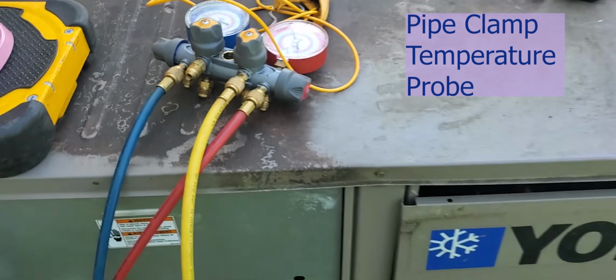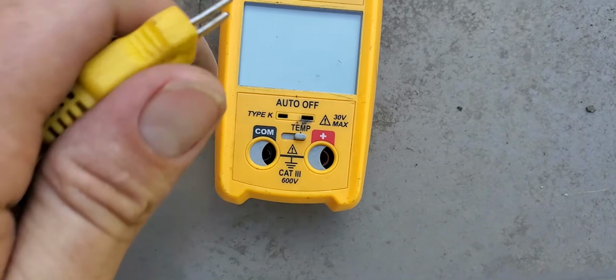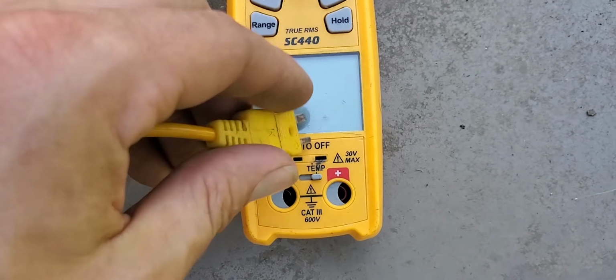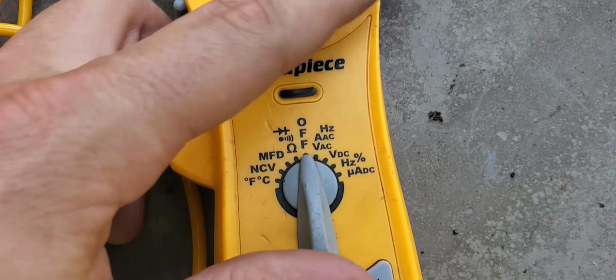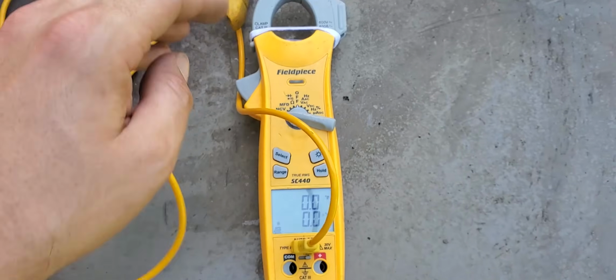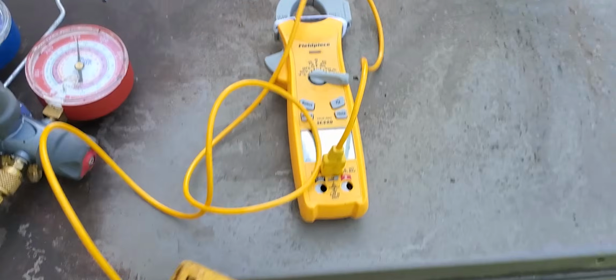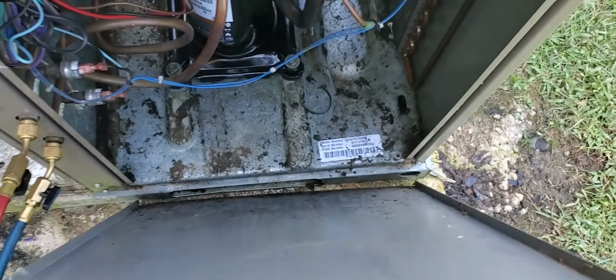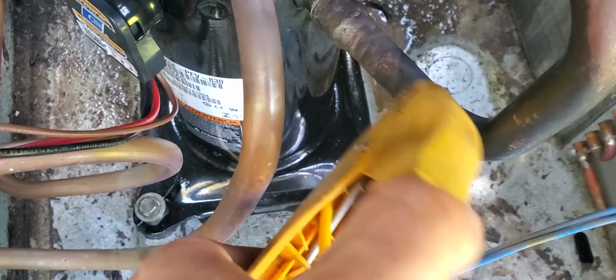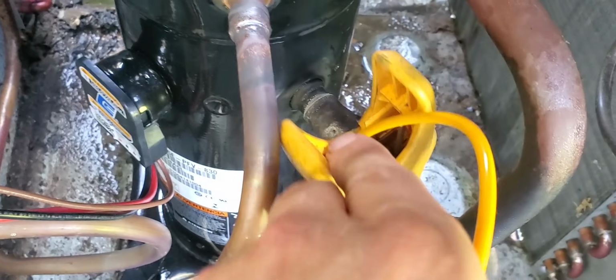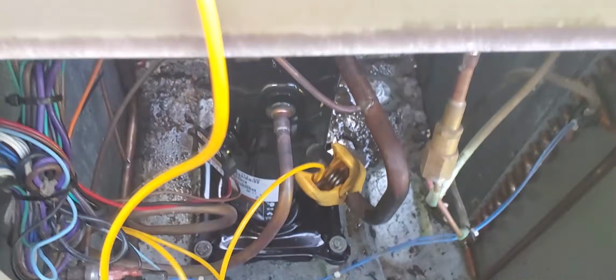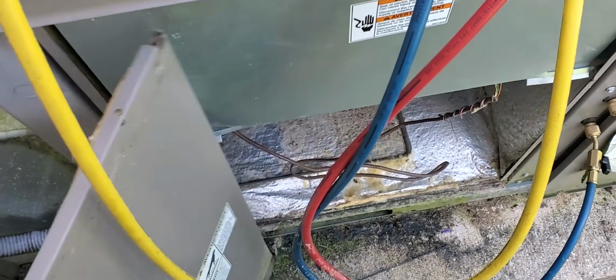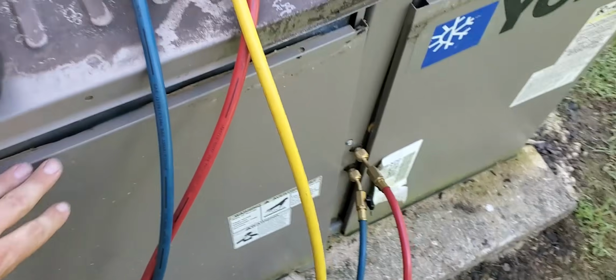Correct refrigerant charge is very important. In undercharged systems where there's not enough refrigerant, the compressor is overworked and it may operate continuously. That leads to wasted electrical energy and also poor refrigeration. Also, with a lack of refrigerant, you can have increased liquid line and drier temperatures. As a result, the drier heats up and some of the moisture it has collected may be released back into the system. In an overcharged system, where you have too much refrigerant, you may have excessive head pressure in the system, also leading to compressor damage.